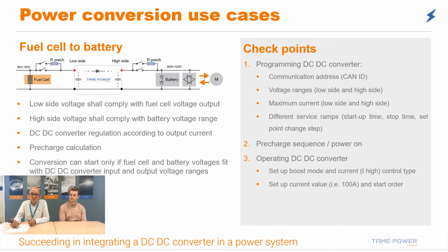We have exactly the same situation on the other side. So when you connect the battery, if you connect directly, there is an inrush current from the battery to charge the internal capacitors. So the battery should be connected through a precharge. Many of the battery systems already include a precharge system with this switch configuration, and that will avoid having too high currents in the DC-DC converter.